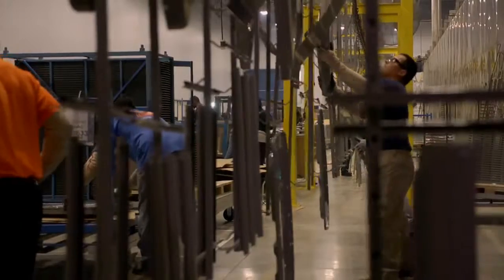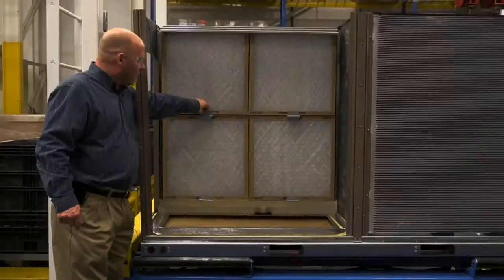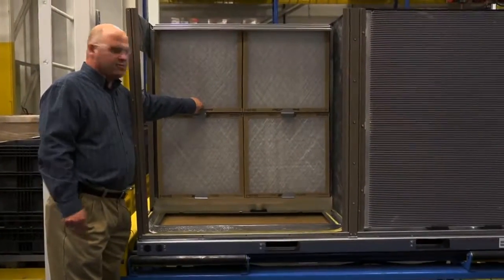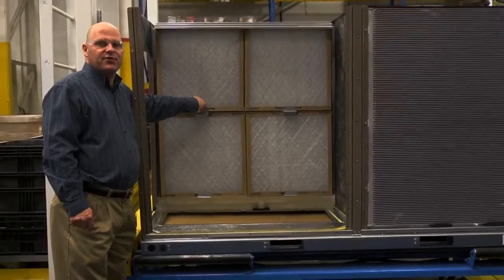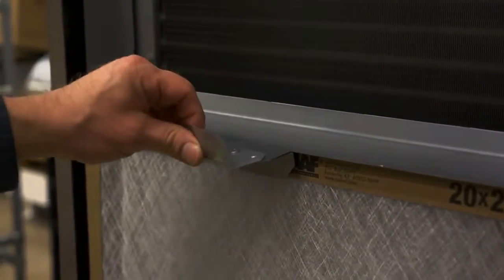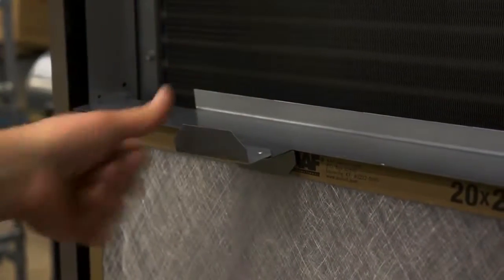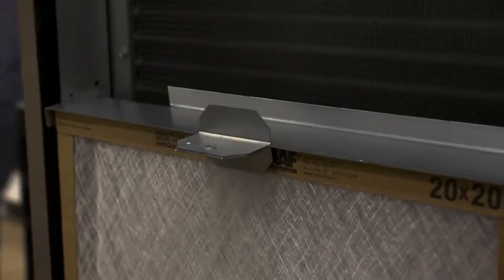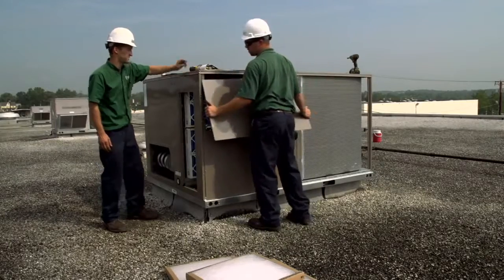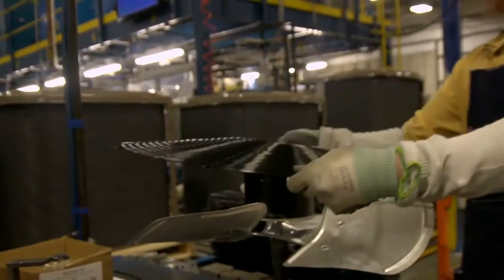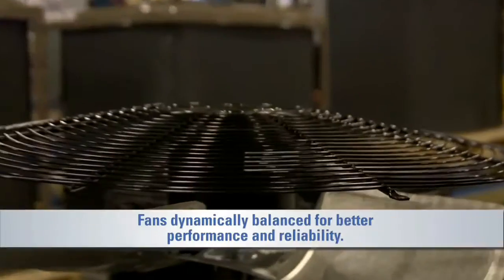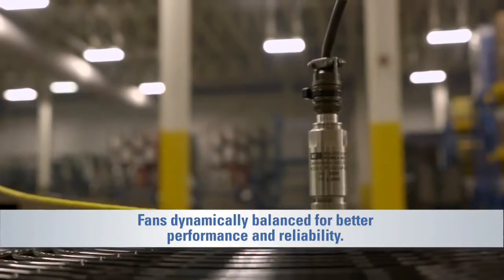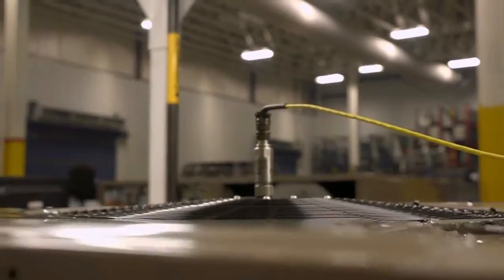Unlike our competitors that have a very similar product that sits on the same footprint, we use both 2 and 4 inch filters. It spins around, and now it becomes a 4 inch channel versus a 2 inch channel. So we can easily convert either here in the factory or the contractors can put them in themselves without doing a lot of work. The quality means it does last a long time. That's the reliability piece of it, and it really needs to be reliable through the whole lifetime of the product.